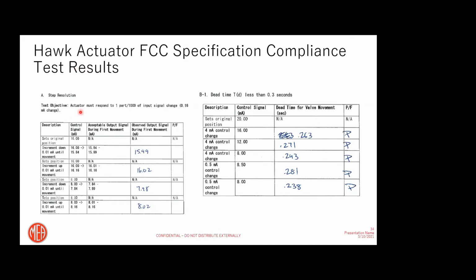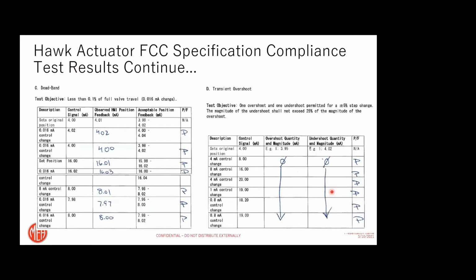As you can see, step resolution, as we said before, every time we change the step by 0.1%, we saw the actual movement of the actuator. That time was recorded here, basically about 0.24 seconds. Dead band, same thing. We ran the test and we saw 0.0 with every 0.016 milliamp control change. We saw the actual movement of the valve.